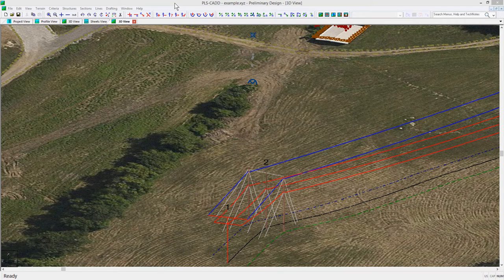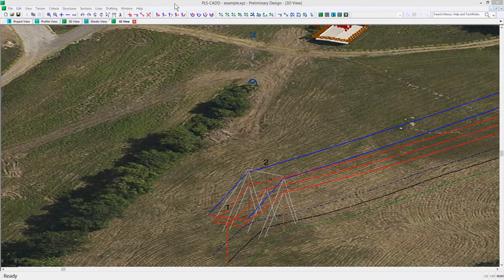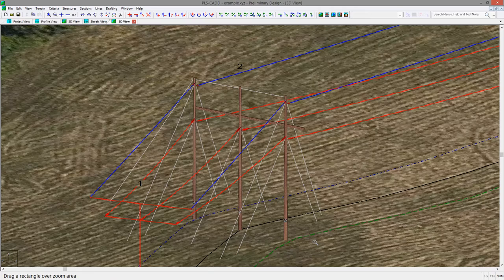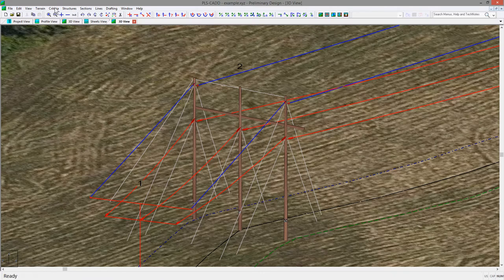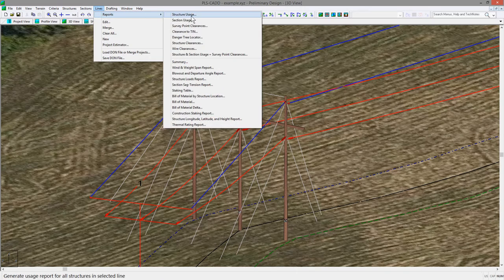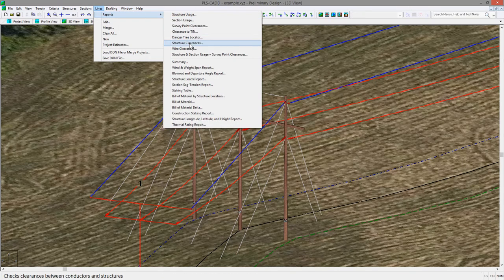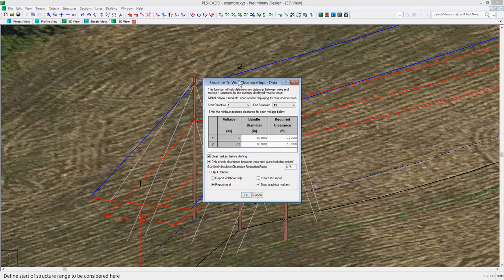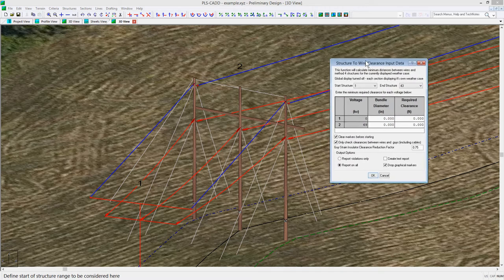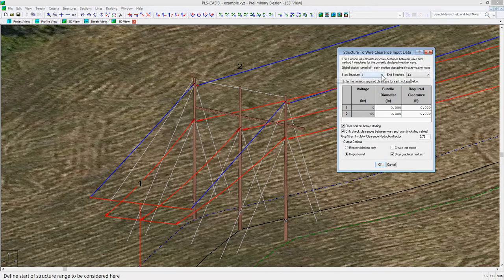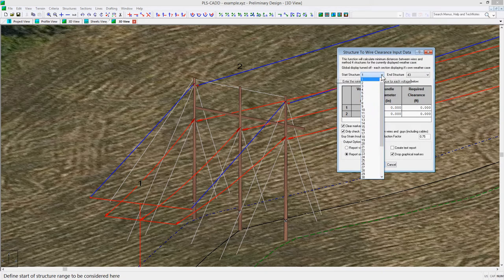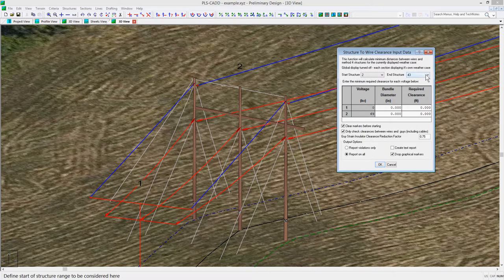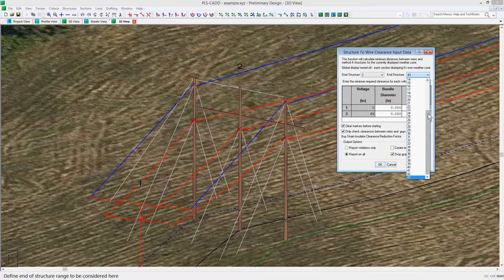Structure 2 is a guyed 3-pole dead end. You can run the Lines Reports Structure Clearances command to check clearances of the currently displayed weather case to all structures in the line. For this example, we will just focus on structure number 2 so we can change the start and end structure accordingly.